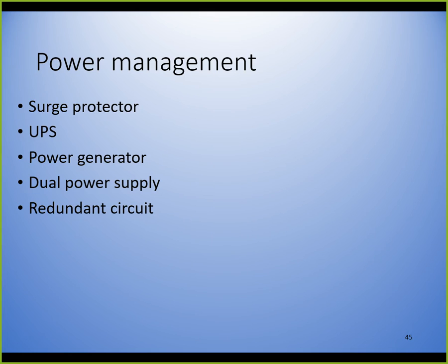If you have a system set up for real failure, you're going to have a UPS, an uninterruptible power supply, so that when the power goes out, you go on the battery, and then the battery starts the diesel generator, and then you switch over to the diesel for a significant amount of time. Hospitals are going to be on generators. Emergency services are going to be on generators. So how much do you need? How long can you be down if there's a power failure?